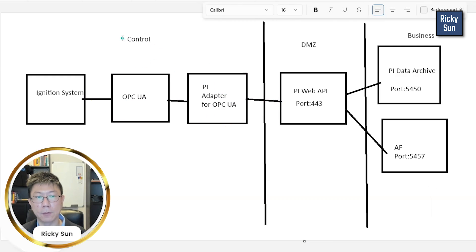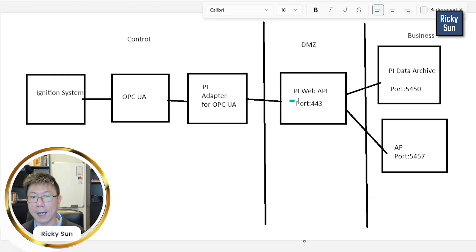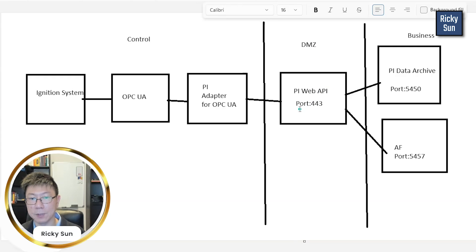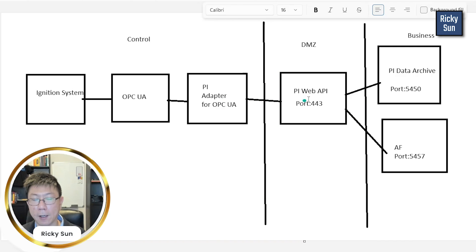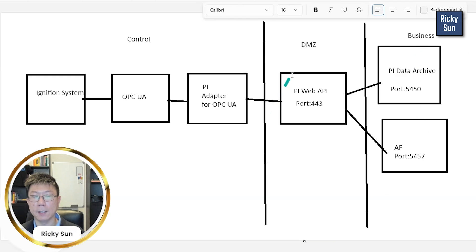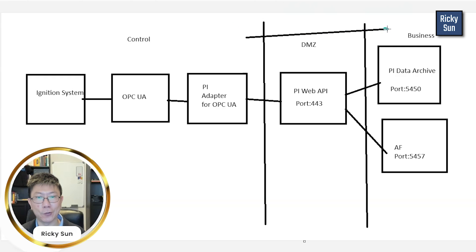The firewall between the control network and the DMZ is one challenge from my perspective, because I have to tell IT I need to submit HTTP requests from the PI Adapters server to the PI Web API on another network, which is in the DMZ. So I need to ask IT to open port 443 — that's the only port you need to open to make the adapters work. I originally had a PI Web API on the business network, but we decided to install PI Web API on the DMZ just to bypass a lot of documentation, because IT would not like us to bridge from the control network all the way to the business network.